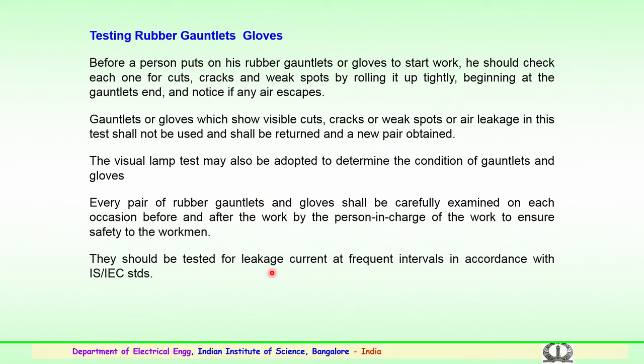Sometimes a visual lamp may be required to determine the condition of gauntlets or gloves. So, several methods are used to check the proper functioning of these gloves and that there is no damage to them. Every pair of these rubber gloves shall be carefully examined on each occasion, before and after the work, by the person in charge to ensure the safety of the workman, which is very important. They should also be tested for leakage current or potential at frequent intervals in accordance with the relevant IS or International Electrotechnical Commission IEC standards.